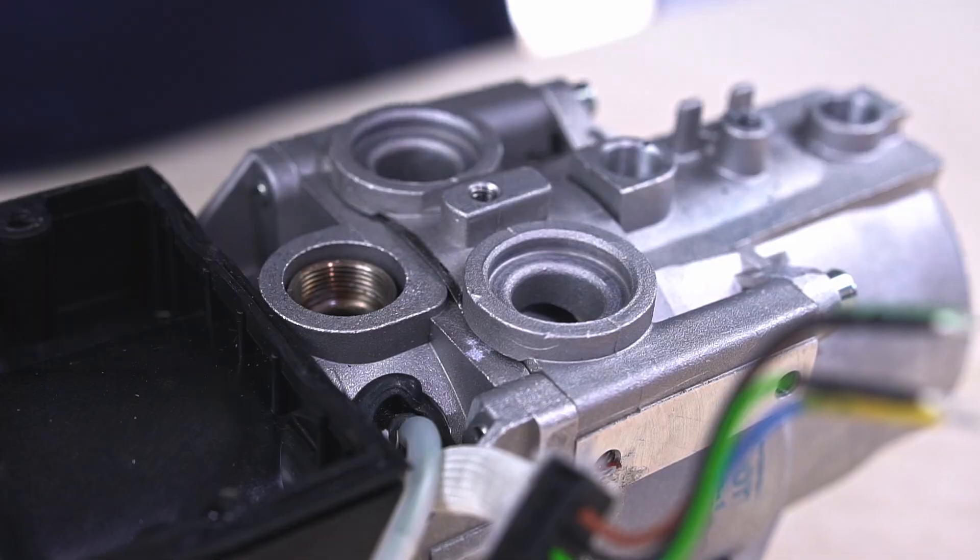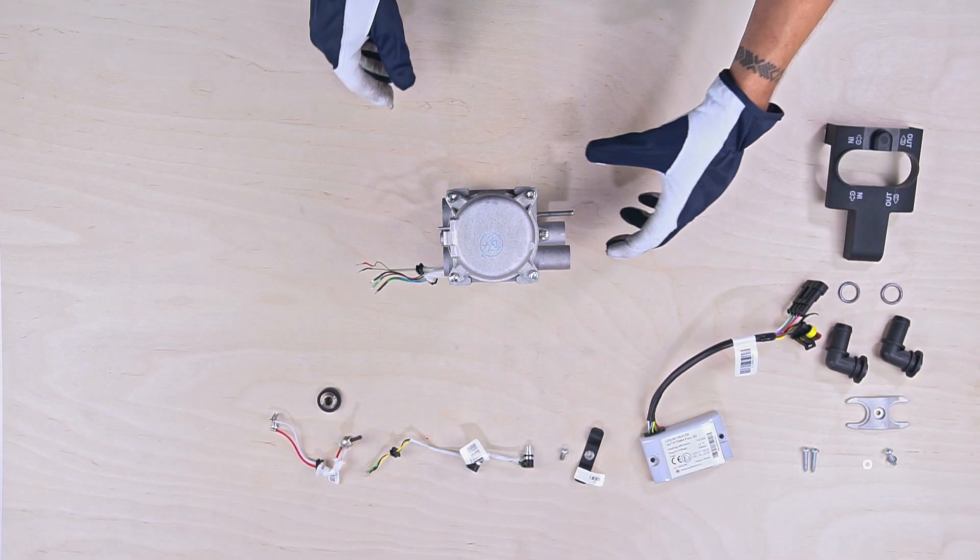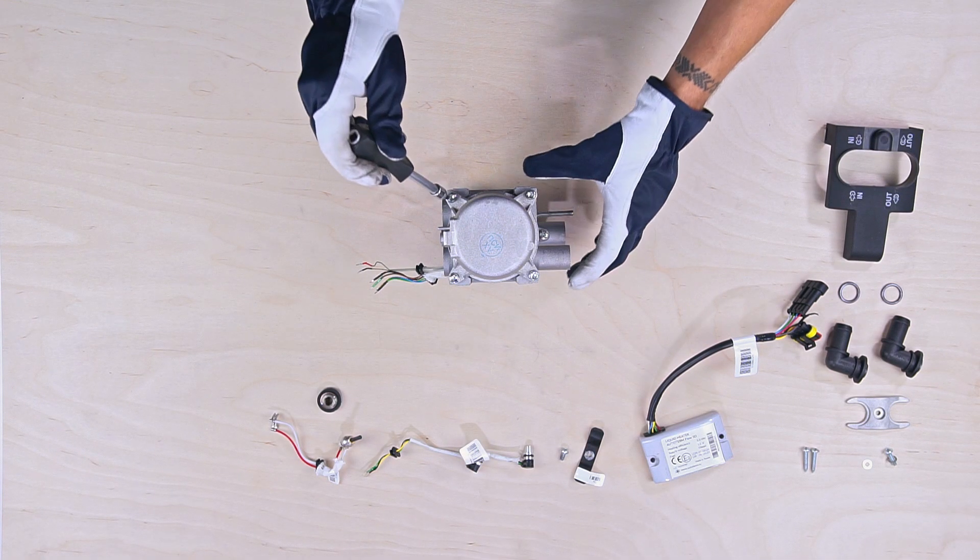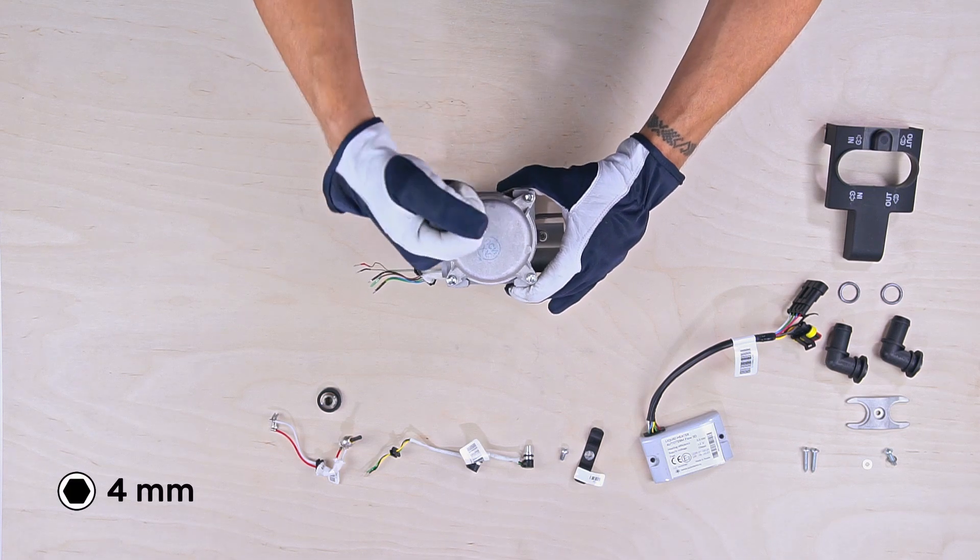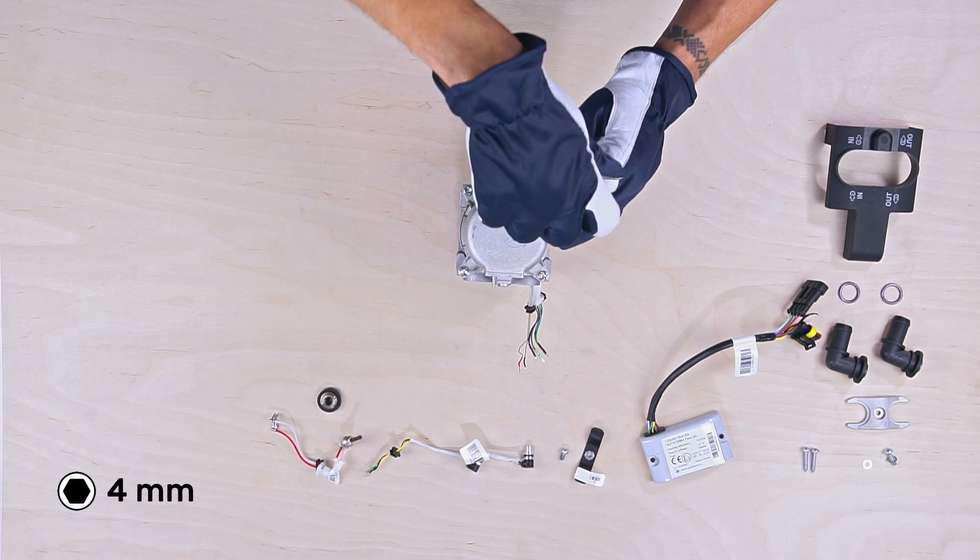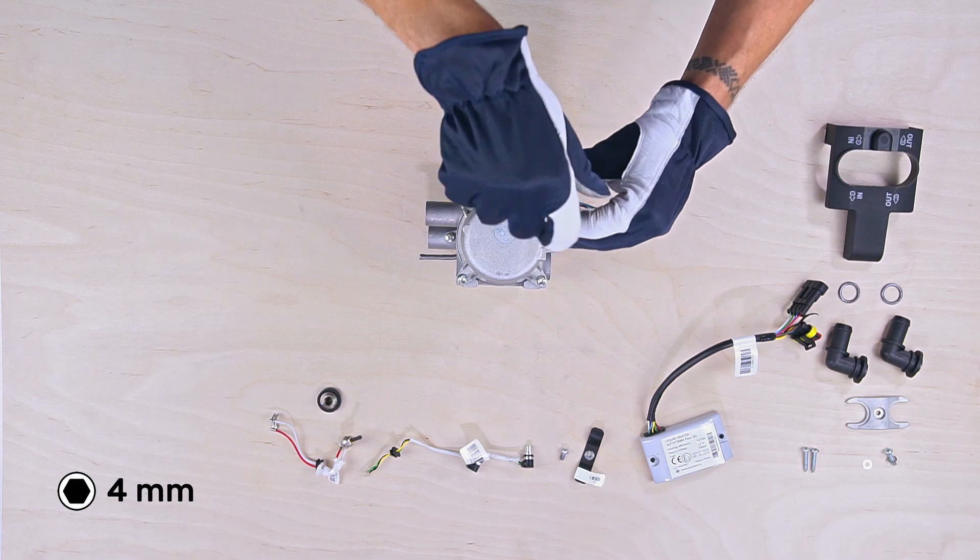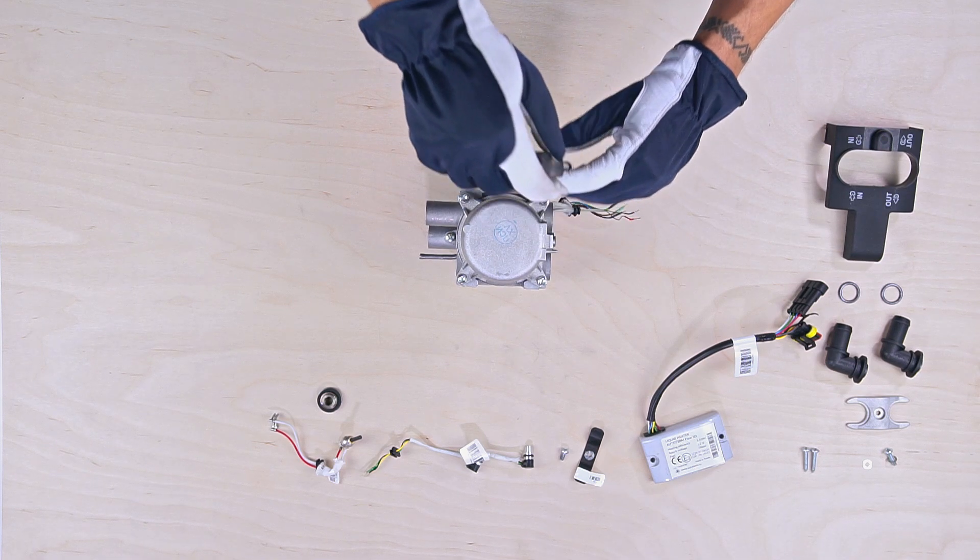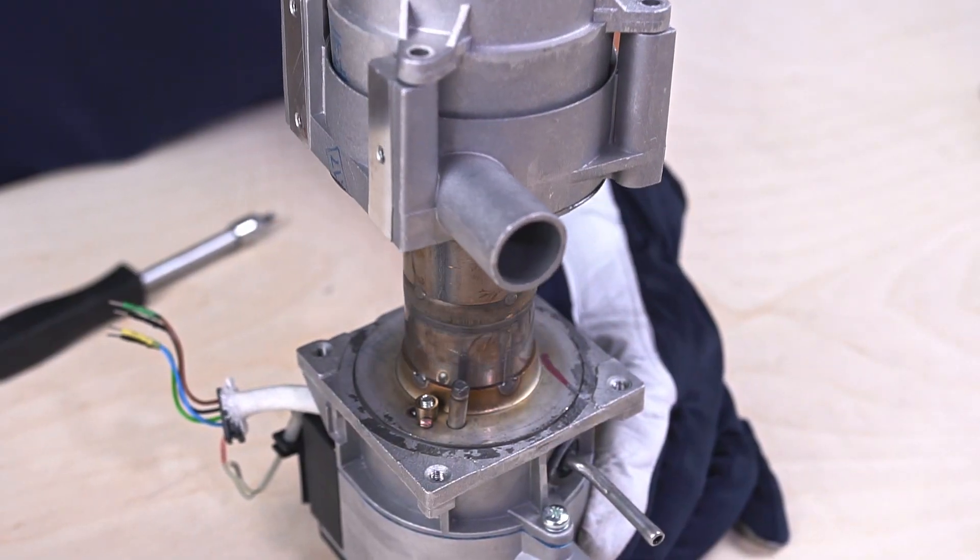When completed, put the heater down with the air pump cover facing down. With the 4mm Allen key, unscrew the four bolts that hold the casing and heat exchanger. Remove the bolts and take off the heat exchanger.